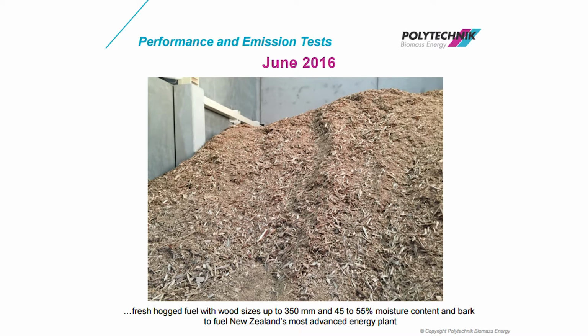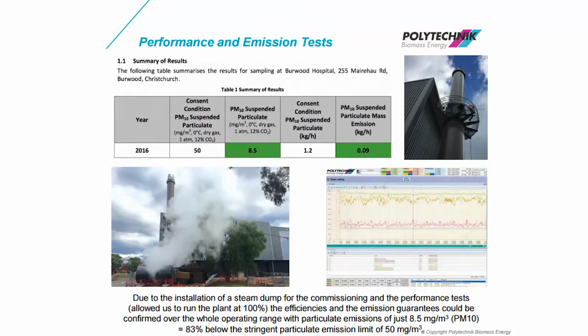So this photo was taken during commissioning. So that fuel's approximately 45 to 55% moisture content. So it's hogged fuel and bark. We ended up finishing the plant, and the hospital was behind with their steam system. So we have a containerised steam dump, which allows us to dump processed steam to atmosphere. So we used this during the commissioning process to generate load, and we could pretty much dial up any load we wanted, which was a benefit during the emissions testing, because we could test right through to the maximum continuous rating of the plant without any issue with not having enough load.